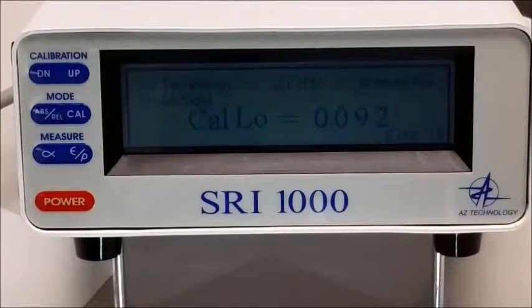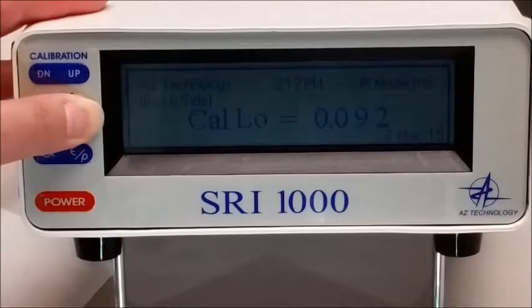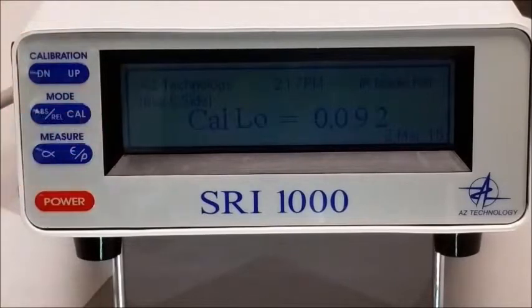Place the black sample black side down, centered on the measurement port. Make sure the displayed Cal low value is the same as the RTH value written on the black calibration sample. If this value does not match the value labeled on the puck container, the value can be changed up or down. Once the value for Cal low is acceptable, press the Cal button for a third time. By pressing the Cal button the third time, the instrument will proceed to measure the black side calibration sample.